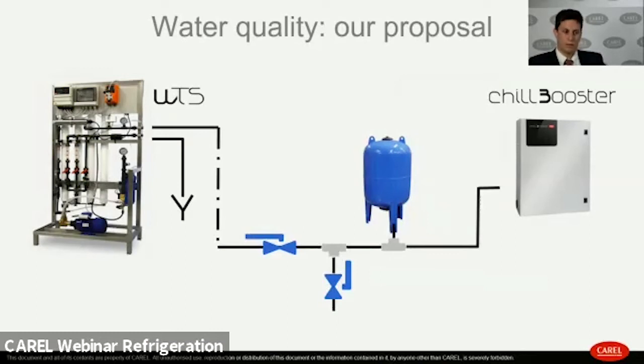Anyhow, the CAREL proposal, in order to minimize the impact and the cost of maintenance, is to use demineralized water in order to avoid any kind of mineral deposits. For this reason, in the CAREL portfolio, there is also the water treatment system, a reverse osmosis plant that is able to filter the water and remove all the solid contents. Together with the water treatment system, the expansion vessel can be installed and provided in order to keep the pressure stable before chillBooster and let it work in the proper conditions.